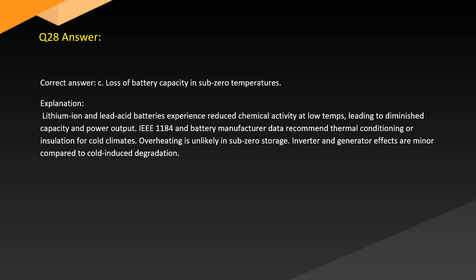Answer. Correct answer: C. Loss of battery capacity in sub-zero temperatures. Explanation. Lithium-ion and lead-acid batteries experience reduced chemical activity at low temperatures, leading to diminished capacity and power output. IEEE 1184 and battery manufacturer data recommend thermal conditioning or insulation for cold climates. Overheating is unlikely in sub-zero storage. Inverter and generator effects are minor compared to cold-induced degradation.